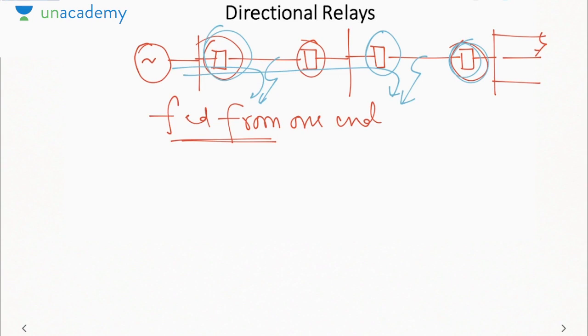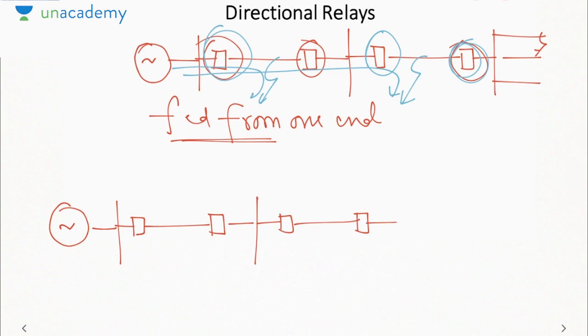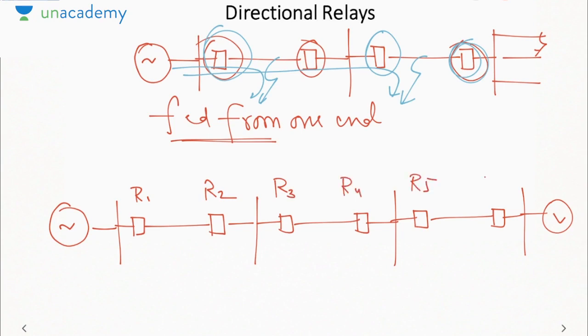But this is not the case when we take the case where the source is fed from both ends. Like this is the system. Suppose this is a system. Here we have 6 relays R1, R2, R3, R4, R5 and R6. Suppose we are drawing load at each bus. Now let us consider two possible cases of the faults. Fault here and fault here. Let us call the faults F1 and F2.